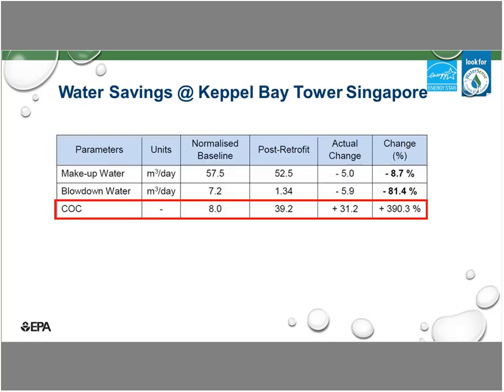The other part that we also save is that, like I mentioned, they were running at 8 cycles of concentration. This is their blowdown, 7.2 cubic meters. Of course, in our system, because conductivity is not relevant to us, we use the makeup water versus the blowdown water. Using conductivity, they recorded 8 cycles. But if you work the ratio of the makeup versus their blowdown, we still get 8 cycles as well. So using makeup water versus blowdown as a way to calculate COC is a correct method, because either way you get the same number.